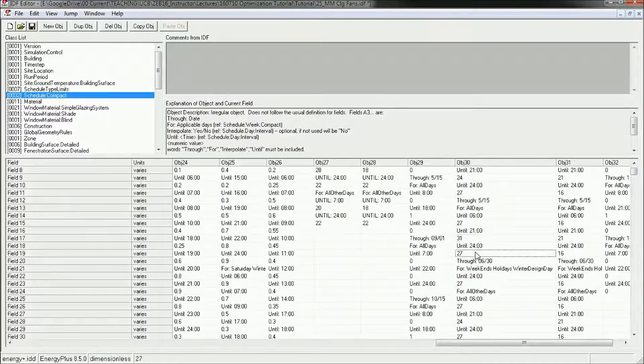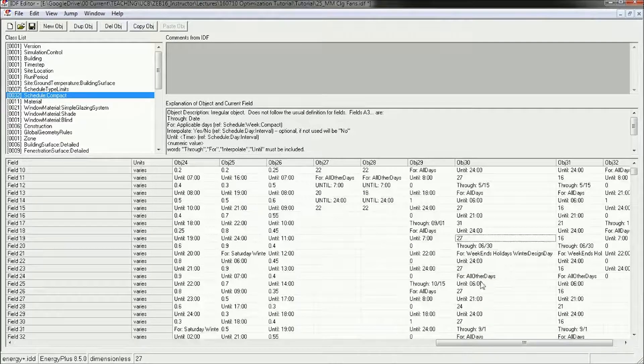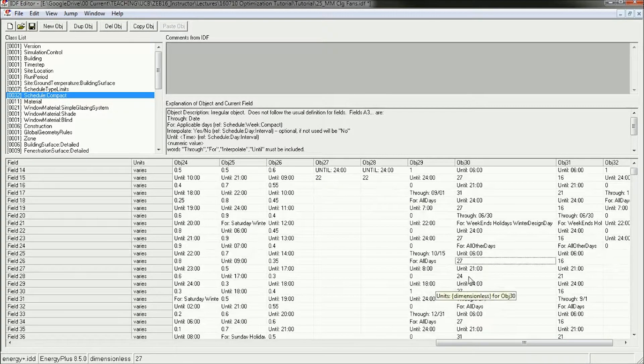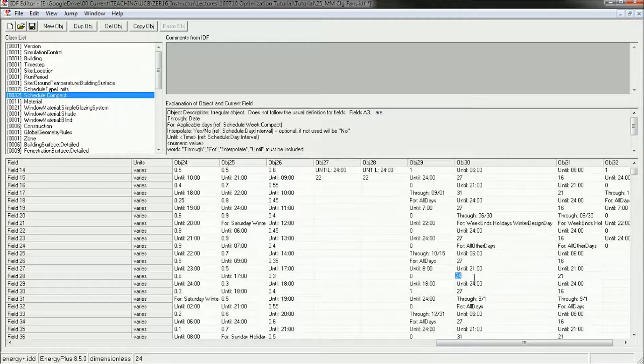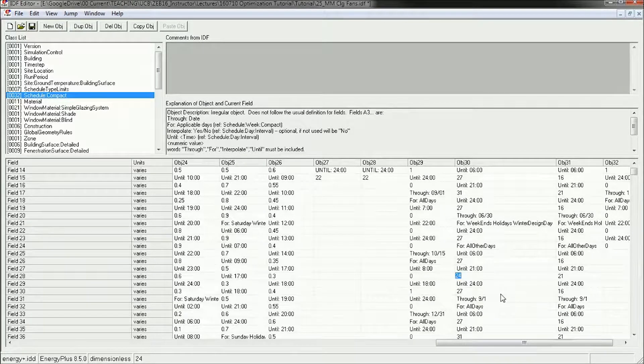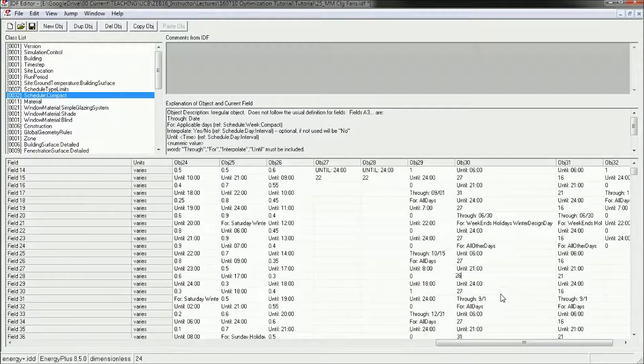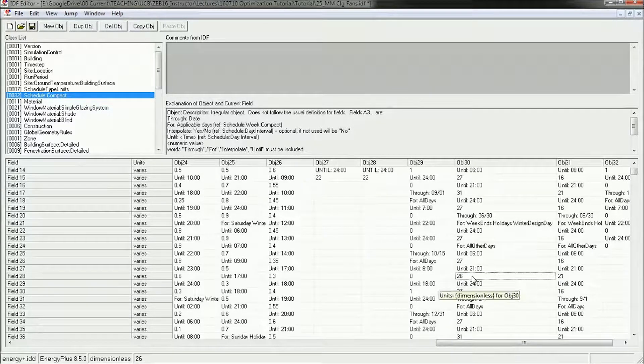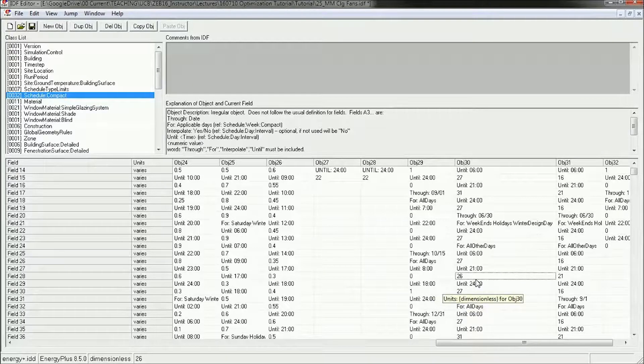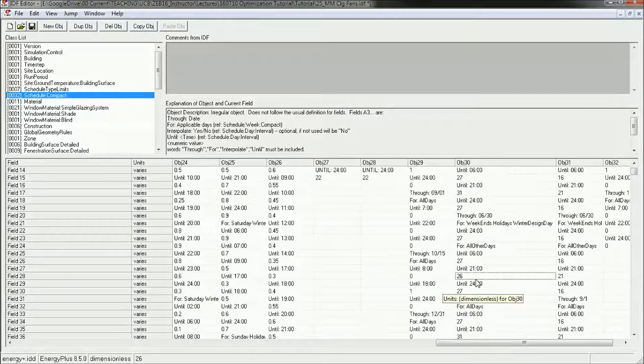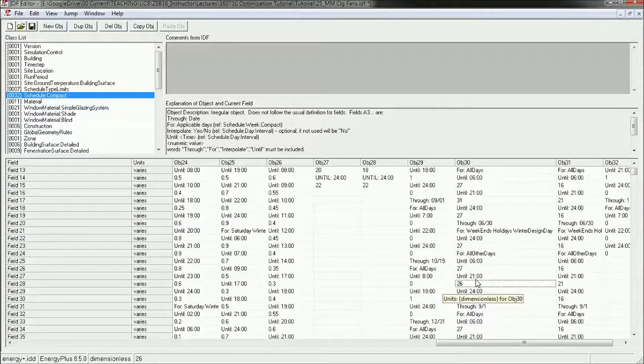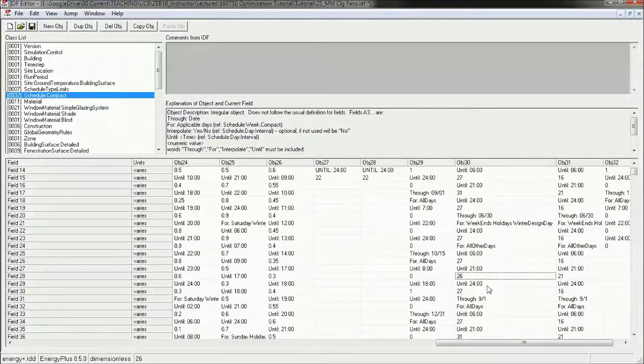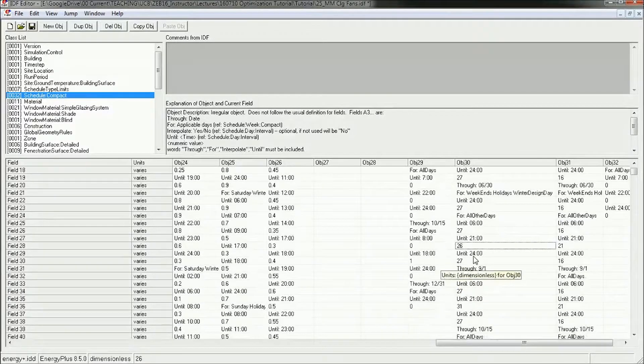And then if we go down through June 30th, these days here from 6 to 9, instead of having a set point of 24, let's make this a set point of 26 degrees. That's 2 degrees of cooling that we're getting out of it. Now during this period, we don't have natural ventilation because the outdoor air is relatively humid, so this is just going to increase air movement inside.